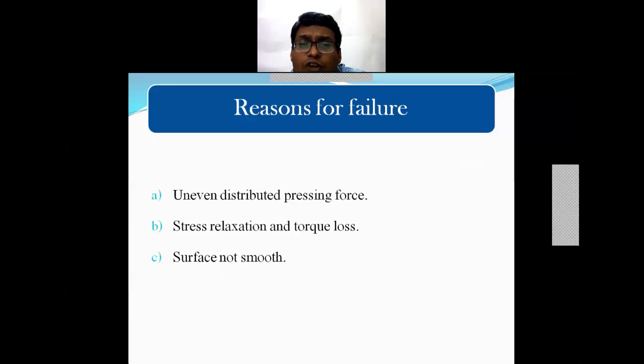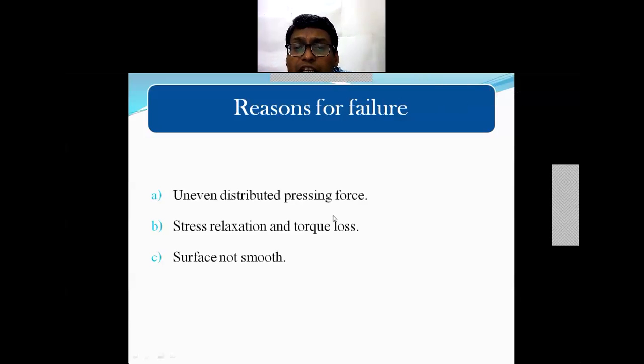Now, there are certain reasons for failure, that is uneven distributed pressure forces. That means in the flange, it should be completely or regularly bolting that has to be done. You have to bolt at this one end, and opposite to that, you have to tighten all these. All opposite bolts, they are to be tightened. But while tightening, they should not be completely tightened. Slightly go on increasing the pressure uniformly. That is, the uneven distributed pressure forces is one of the major reasons for failure.